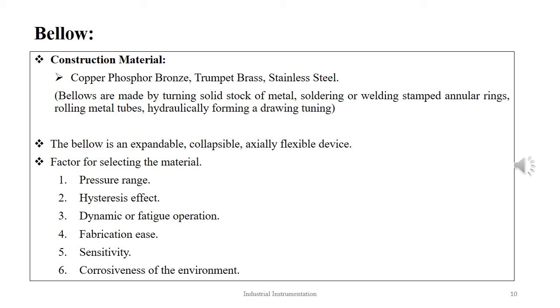For selecting the bellow material, the following factors are checked: the pressure range under measurement, the hysteresis effects, the fatigue or dynamic operation, the corrosive environment and how corrosive the environment is, ease of fabrication, and sensitivity to fluctuating pressure.